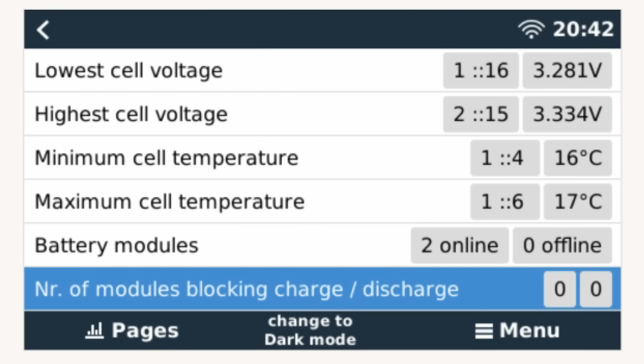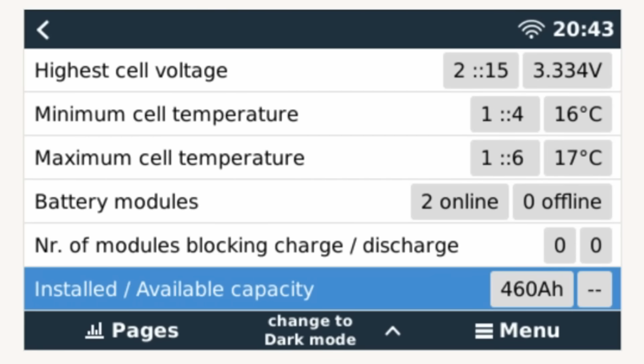None of them is blocking charge or discharge. The installed capacity shows as 460 ampere hours. I have flagged this with Jaki already - this is of course not correct, because we have a 230 ampere hour battery with a 100 ampere hour battery in parallel. But the master battery only knows there's another battery connected and assumes it has the same capacity as itself. Hopefully they can fix this with a firmware update, and then it will show the correct combined capacity of both batteries.